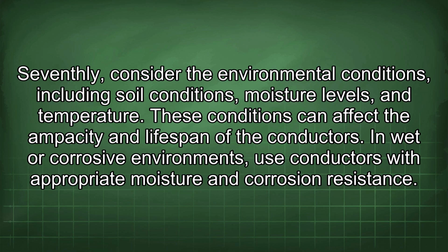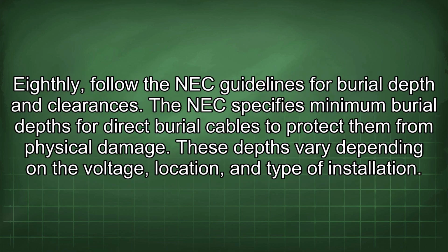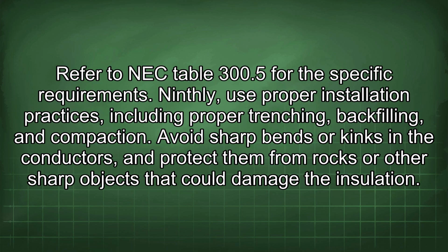These conditions can affect the ampacity and lifespan of the conductors. In wet or corrosive environments, use conductors with appropriate moisture and corrosion resistance. Eighthly, follow the NEC guidelines for burial depth and clearances. The NEC specifies minimum burial depths for direct burial cables to protect them from physical damage. These depths vary depending on the voltage, location, and type of installation. Refer to NEC table 300.5 for the specific requirements.